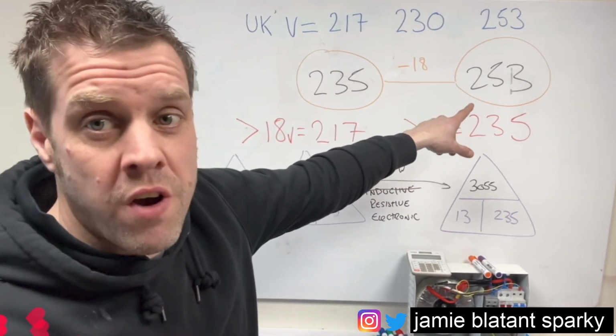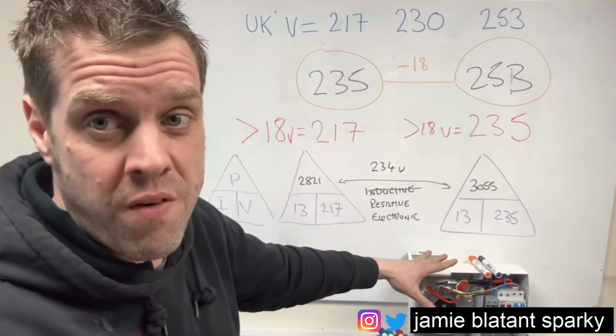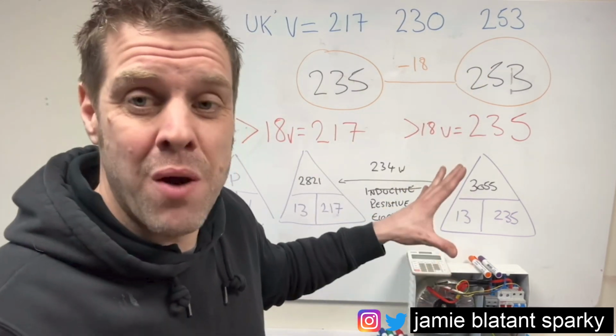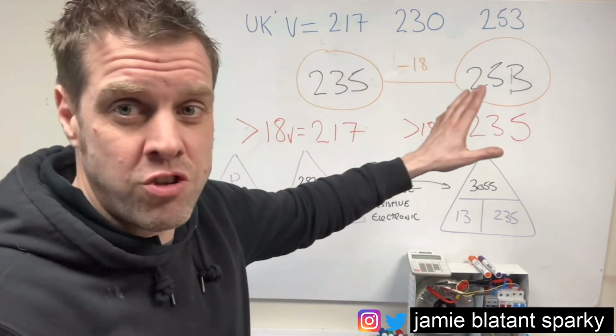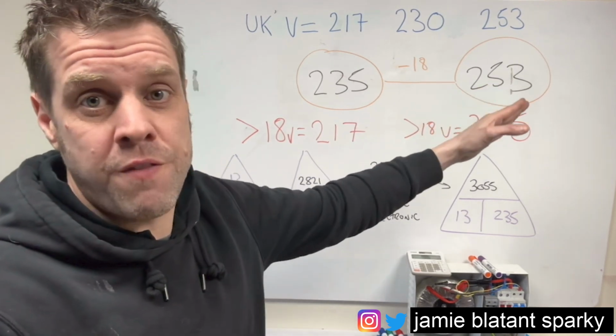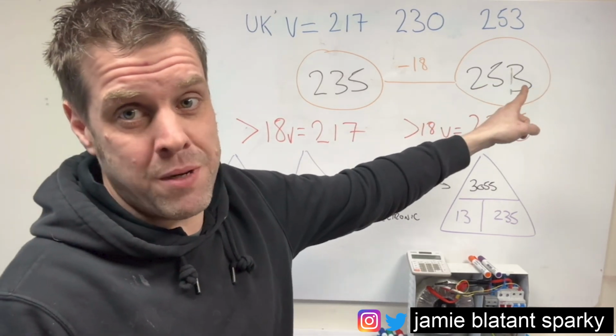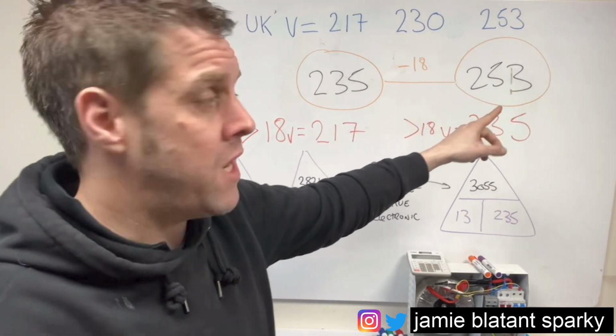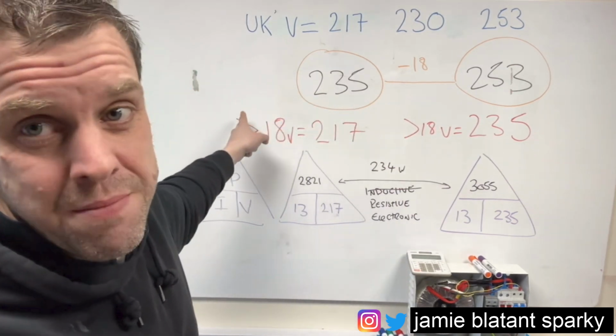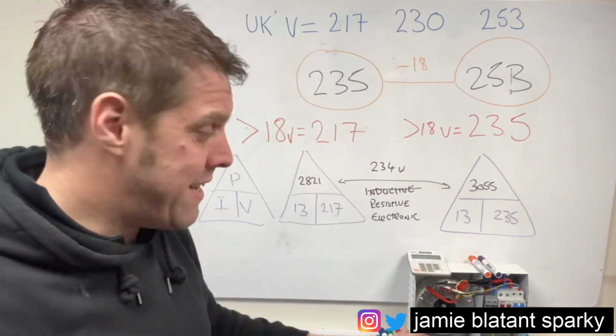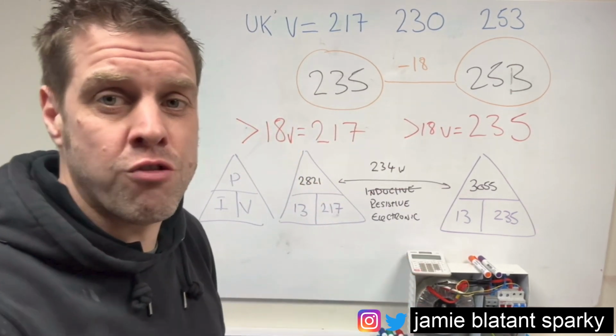It can't be used when you've got over voltage because it doesn't function over voltage, it's designed to work on the UK grid, which means it's got to be within the right voltage range. All it will do is bring your voltage from the maximum down to this number, 235, or from 235 down to the minimum, 217. It doesn't have any electronics in it. It doesn't fluctuate with the voltage.